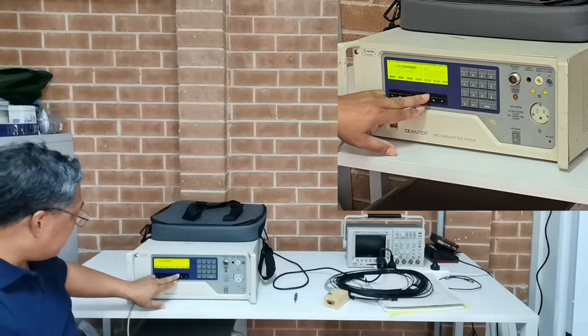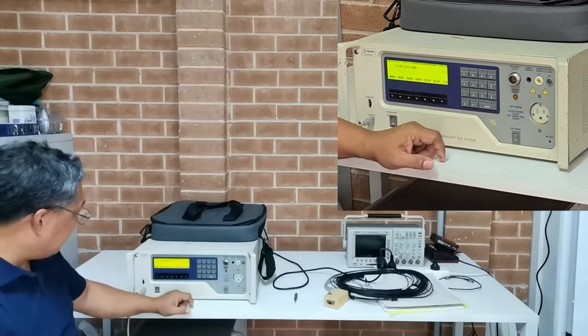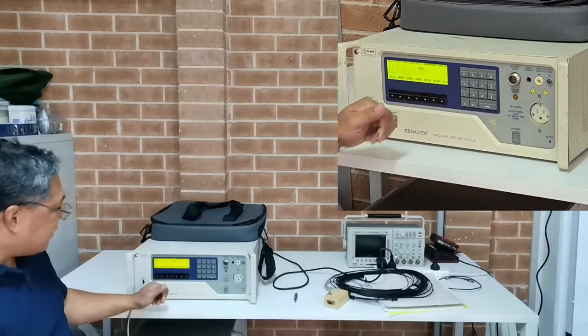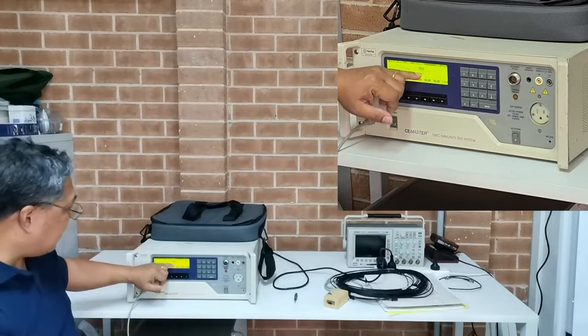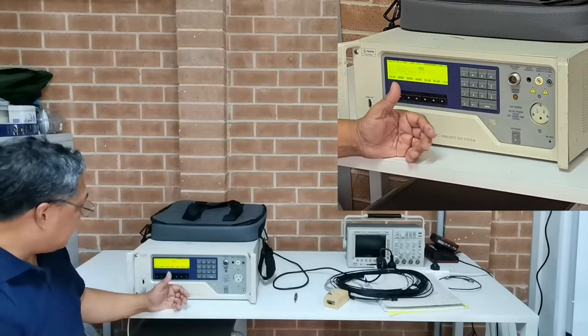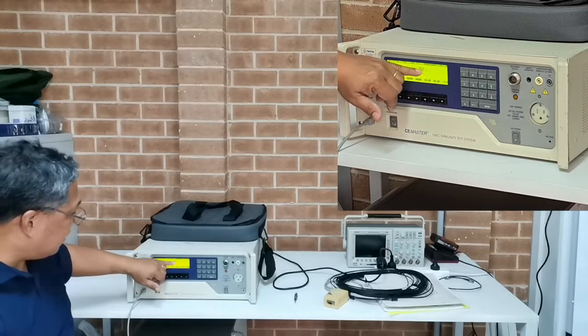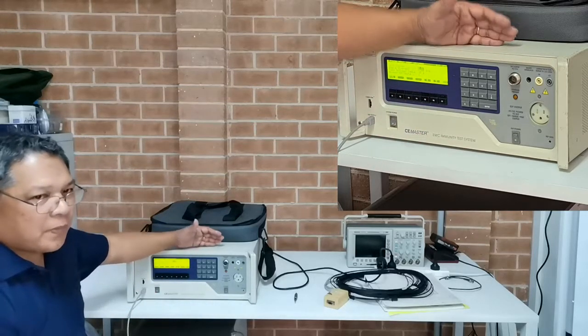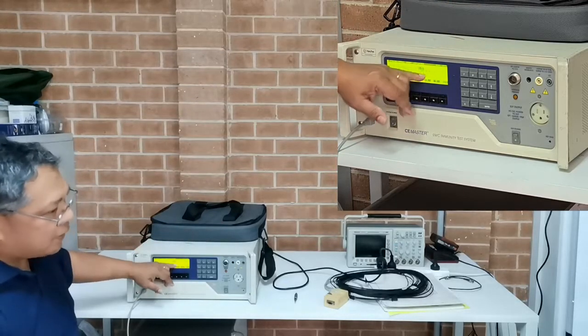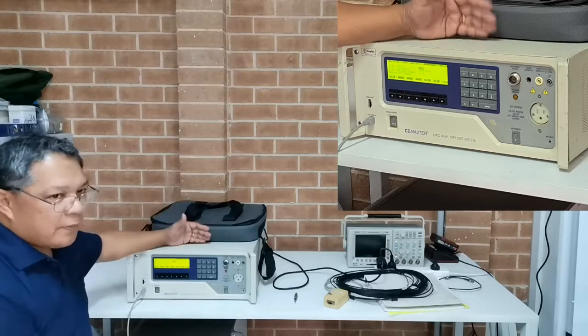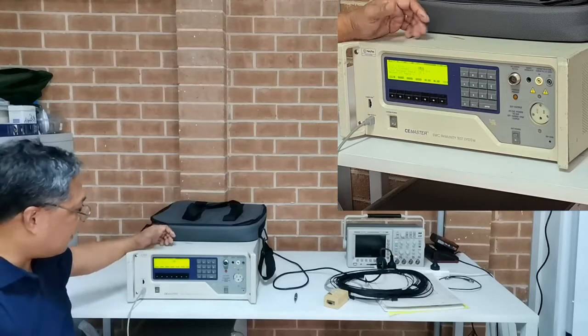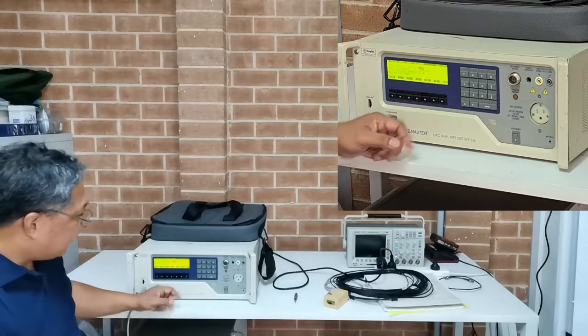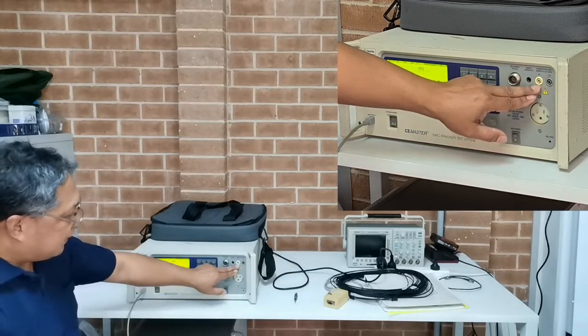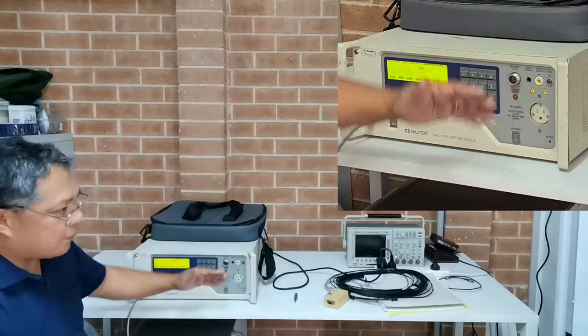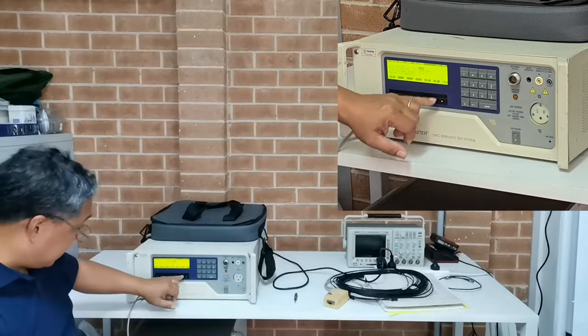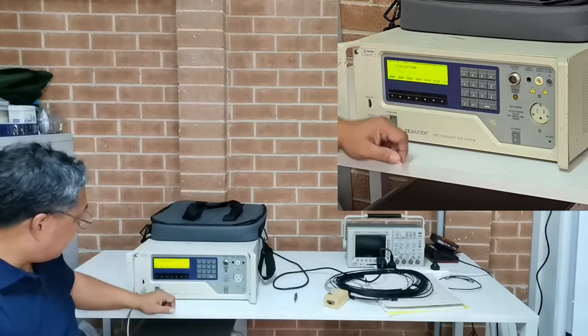So the sixth one is the pulse magnetic. We'll try that. Oh, it's great. It's working fine. With pulse magnetic, you can set the requirements like 100 amps per meter of pulse at 1.2/50 microseconds, and you can also set the power factor. But the new KeyTek EMC Pro Plus and EMC Pro don't have this. They might have it, but the card doesn't come with this option. You can purchase an additional one to get this option working, and this is very handy, as we can connect the magnetic loop here and do the pulse magnetic test. Pulse magnetic is 61000-4-9. So we'll exit that one.